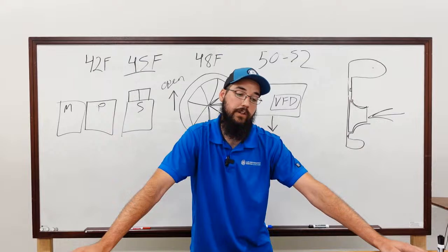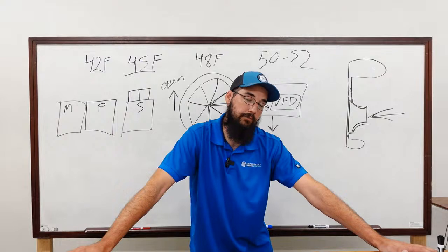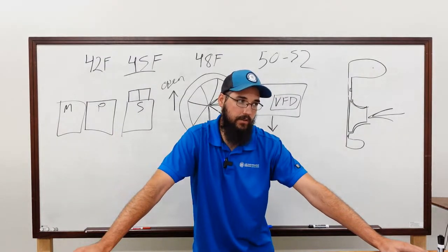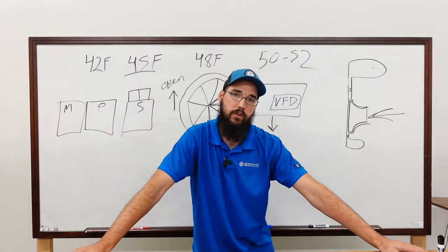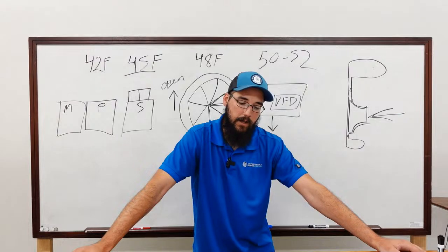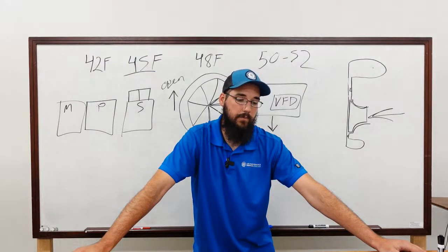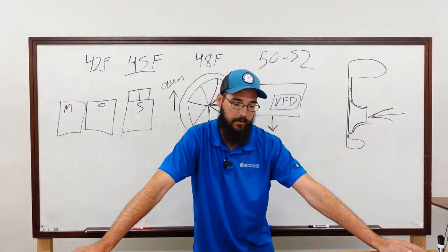The recovery didn't freeze the tubes. The freeze did. And the power failed to the building. So it froze for different reasons, but the results are the same. The refrigerant flooded the chill water loop and overpressurized it, caused all kinds of water leaks and damage because of the loop pressurizing so high. But at the same time, it literally filled the chiller with water. The craziest thing I saw, you pushed in on the liquid line and you just had water shoot out at you in the Schrader. It's bad.